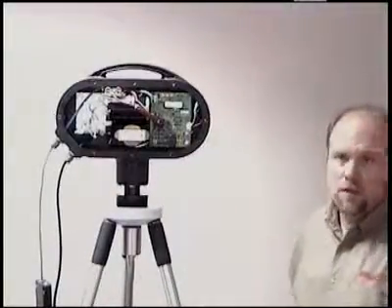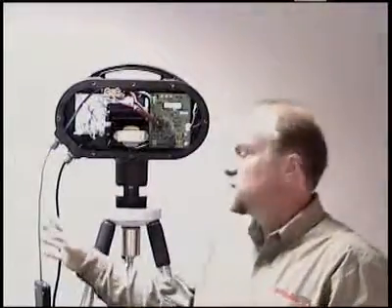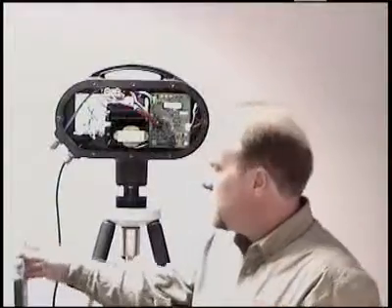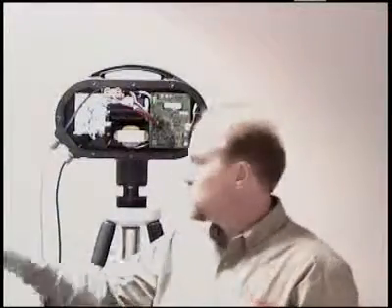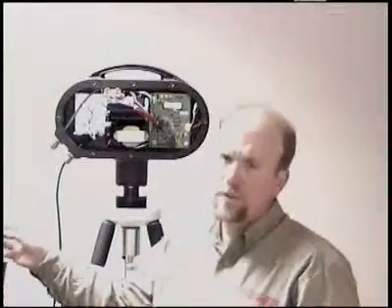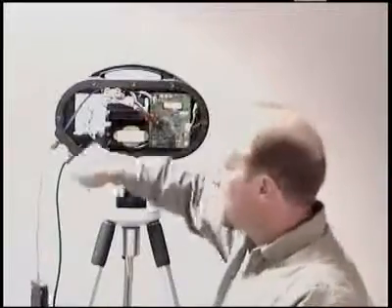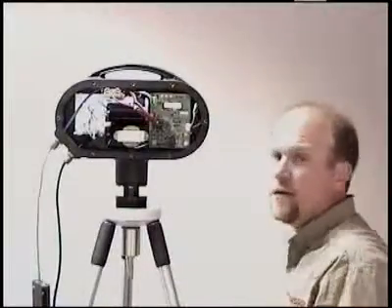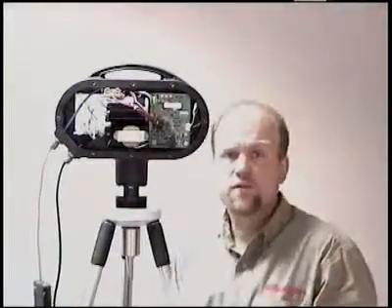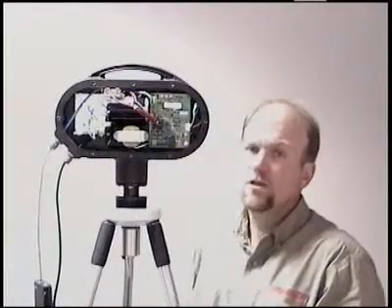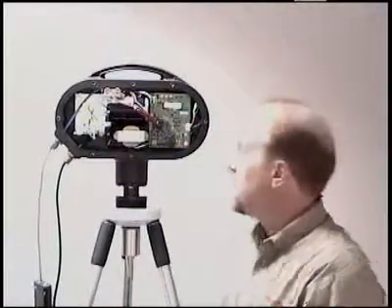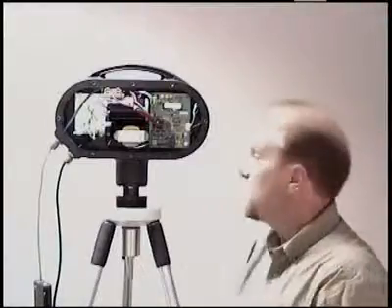Electronic features. We operate on an RS-485 network, meaning that from our control source we run a twisted pair shielded communication line in series to each remote, daisy chained together. We can run up to 4,000 feet and depending upon the communication source, we can operate up to 128 remotes on one network.